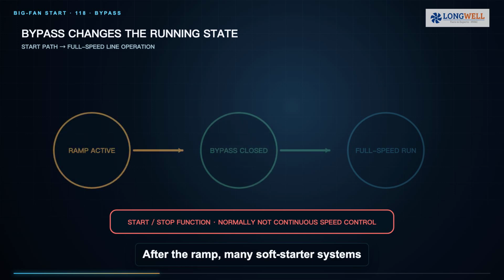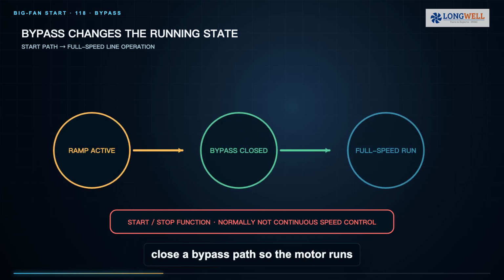After the ramp, many soft starter systems close a bypass path so the motor runs from line frequency power with lower losses in the starter. That makes the soft starter primarily a start and stop device, not a continuous fan speed controller. The exact bypass contactor, protection, thermal model, and switching sequence must follow the selected product design.